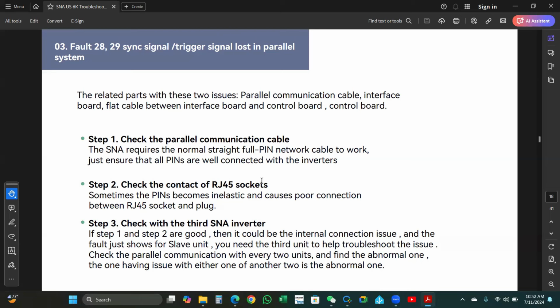Step one, check the parallel communication cable. The SNA requires a normal straight 4-pair network cable to work. Just ensure all the pins are well connected with the inverters. Step two, check the contact of the RJ45 socket. Sometimes the pin becomes inelastic and causes a poor connection between the RJ45 socket and the plug.